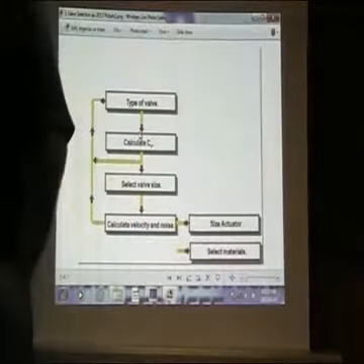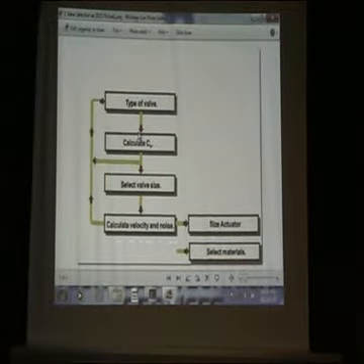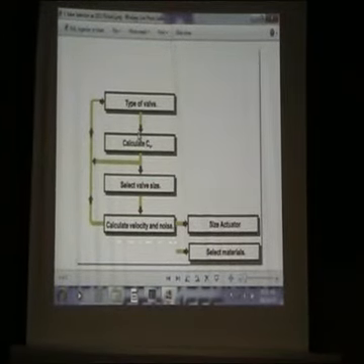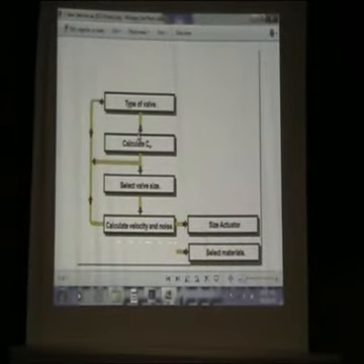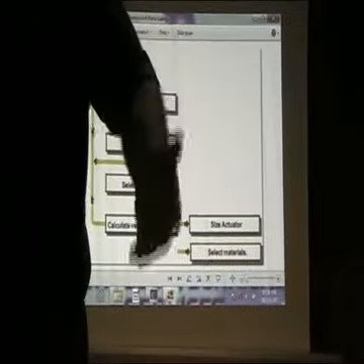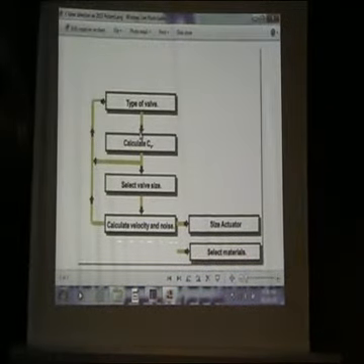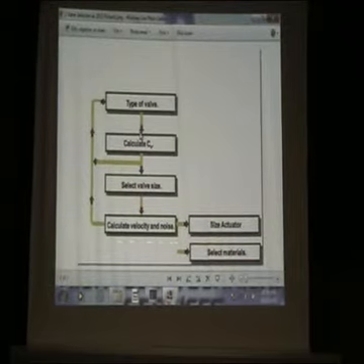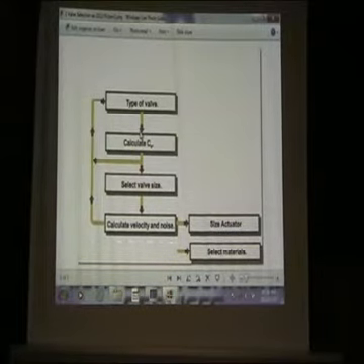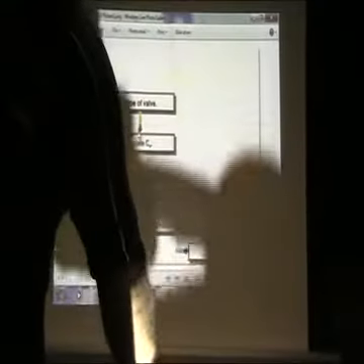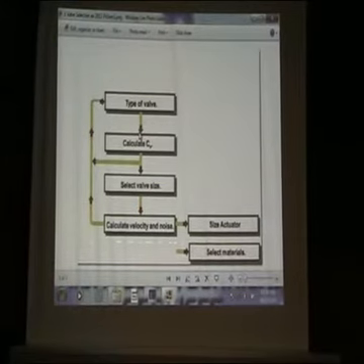Okay, so type of valves, flows. We say pressure. Media. What's going through, absolutely, why? Because it makes you decide what type of valve you can use. Let's say you can't get a Stellite butterfly, but you can do it in a control valve. It depends again on on-off, modulating, whatever. But yes, pressure is important because you don't want to put this valve on a 30 bar application that can only handle 10 or 15 bar. You're wrong.